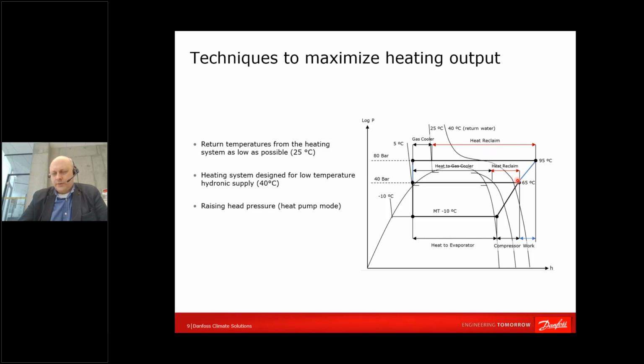How do we relate that chart with our heat recovery? If our heating system or HVAC system is returning temperature to the plant with a value of, for example, 40 degrees, what do we see here? We see that we have a potential for the heat reclaim. So as we can see, there is not much we can reclaim. And therefore, if your heating system would be designed for even lower temperatures, for example, 25 degrees, now you see that the potential for the heat recovery has increased.